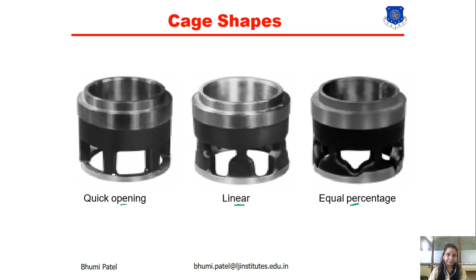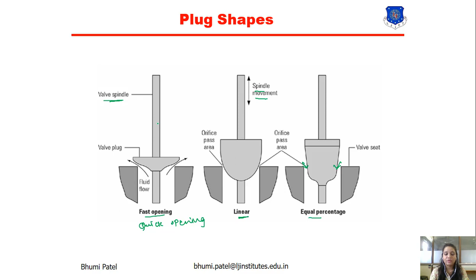Now same like the cage, different plug shapes are also available for the characteristic application. Here three types of plug shape are given. First one is the fast opening or quick opening. Here you can see that the gap between the inflow and outflow is low compared to the equal percentage. For the linear characteristic, the inflow and outflow gap will be the same, and for the equal percentage, whatever the input flow is, we can get the equal percentage output. Now we can move the valve using the spindle movement, so we connect the valve spindle to the valve plug. So these are the different types of plug shape for the valve characteristic.